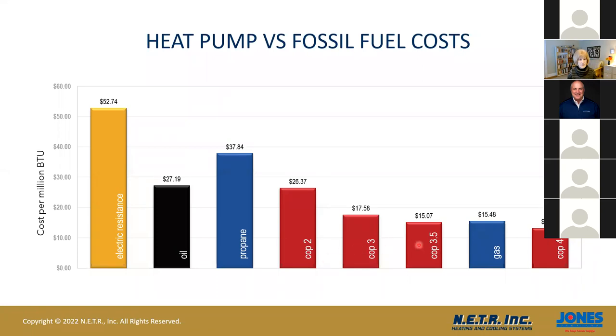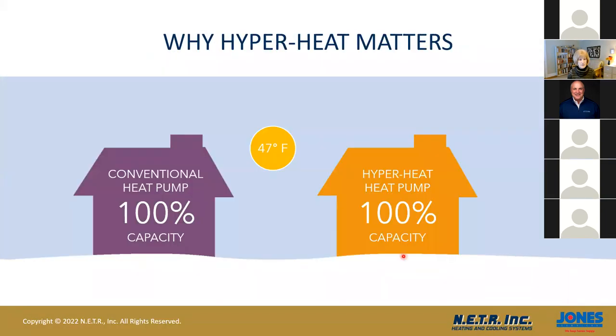So I want you to keep in mind these COPs, because when we look at the ratings of heat pumps and how they are rated, they're rated at different temperatures. Now, most manufacturers have a rating at minus 5 degrees, 17 degrees, and 47 degrees. And that's when they're going to show you the efficiency of the heat pump. So there are a lot of manufacturers that have heat pumps that can provide the amount of BTUs that the system will operate at, at 47 degrees and 35 degrees. When you start to get down below certain temperatures is when the heat pumps lose efficiency.